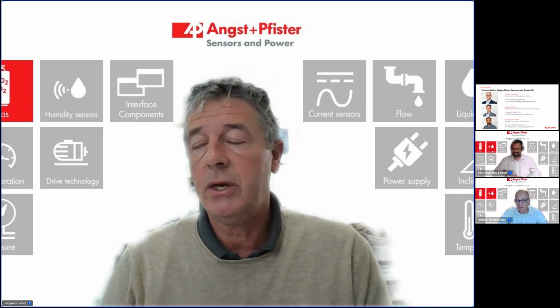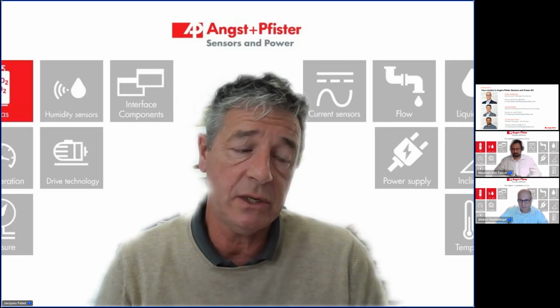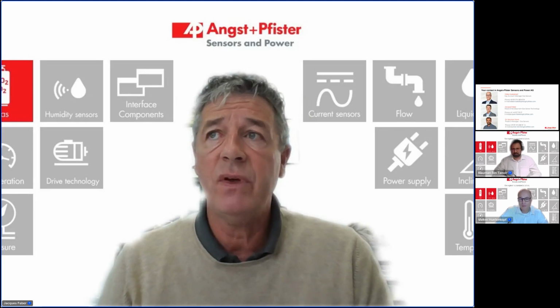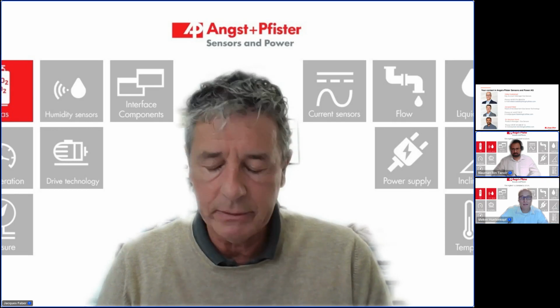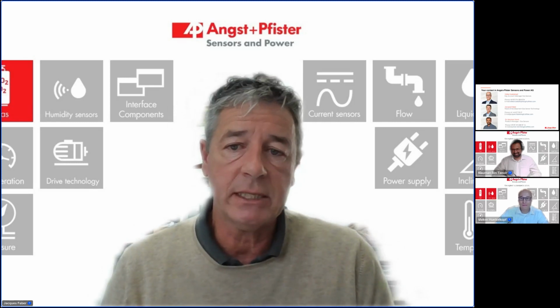So if someone wants to have a fast measurement, there is a question here. What is a typical T90 rise time for paramagnetic sensors? This also cannot be answered with just one figure, but if you have just a sensor itself, with a quite small pathway, then you will get a reasonable result within 3 minutes. Sorry to cut you. 3 minutes, you said? 3 seconds, sorry. Okay, that's very important. Sorry, 3 seconds. And if you have the sensor built into an analyzer with a quite long pathway with a filter and so on, then it might take up to 10 seconds. It somehow depends.